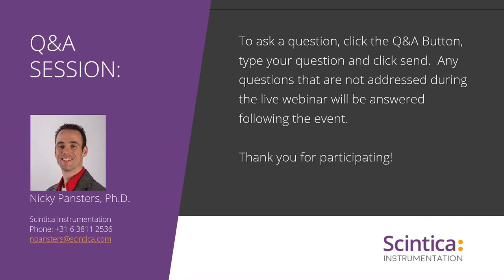Thank you for the question. Yes, the angle correction when you're using basically a one-dimensional imaging of the Doppler flow velocity is basically you don't, unless you really know the angle that you're approaching at. And saying I don't is very contradictory to explaining and focusing on the angle correction being of very much importance when using Doppler flow velocity. But with the use of a dedicated Doppler flow velocity system, you would have probes that are very small and allow you to approach your measurement direction at a very sharp angle, so an angle of 15 degrees or even less.